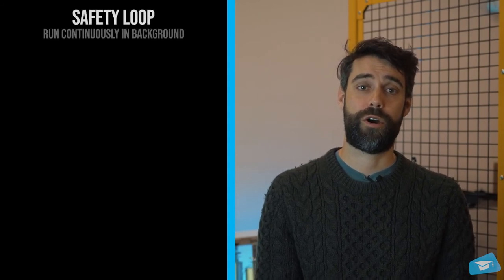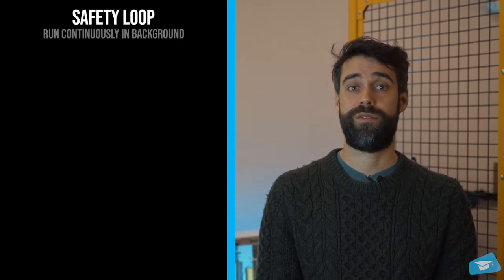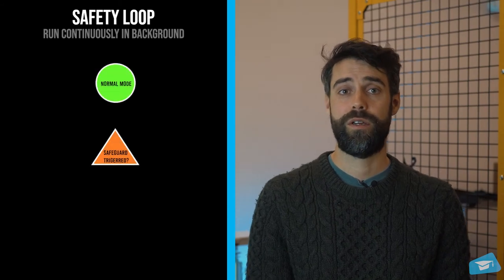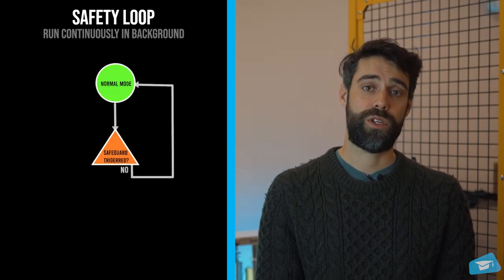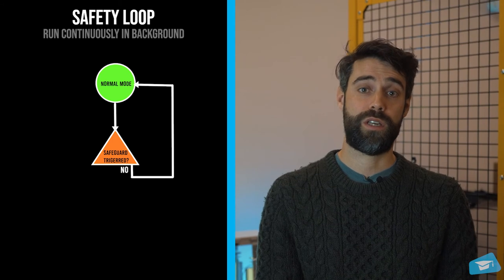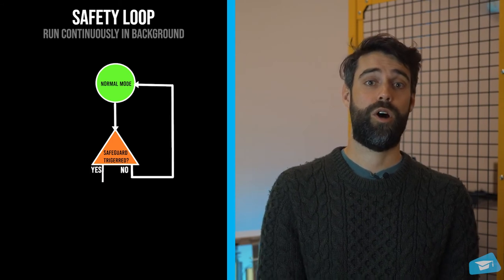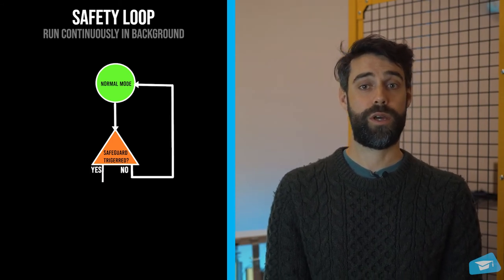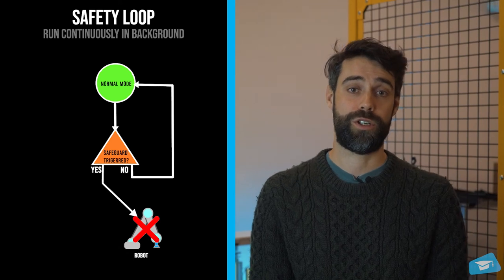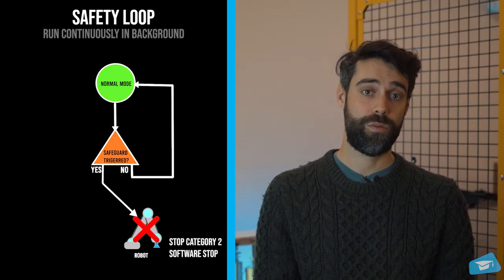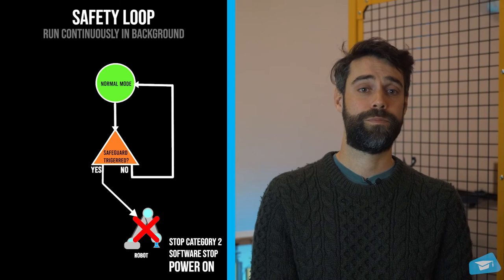The Robotiq Palletizer is intended to work with safeguarding. Various setups for safeguarding will be explained later on. Whatever the setup used, the safeguarding device will trigger the safeguard stop of the cell. Upon that trigger, the robot will stop its motion and hold its position. That's a stop category 2, a software-controlled stop.